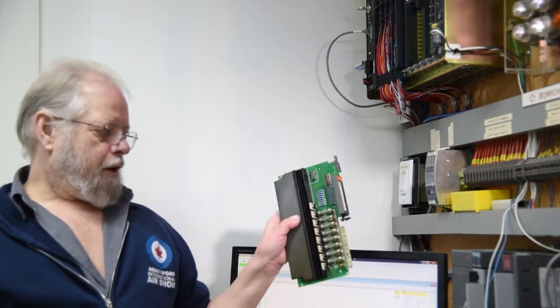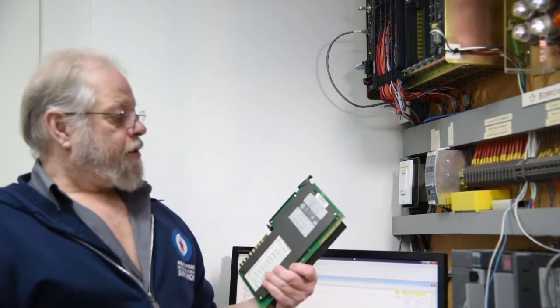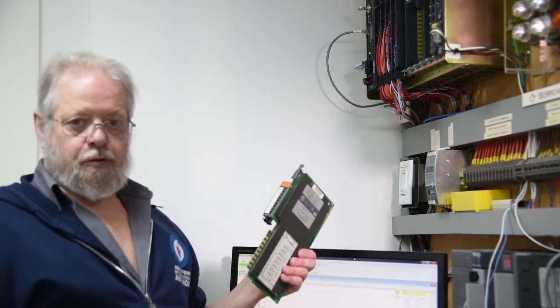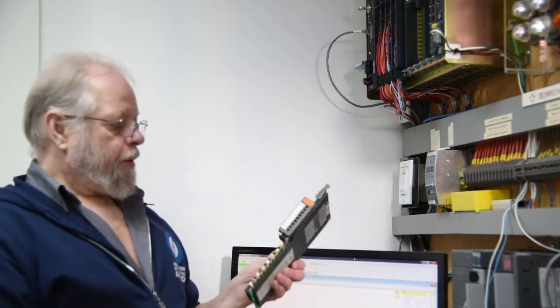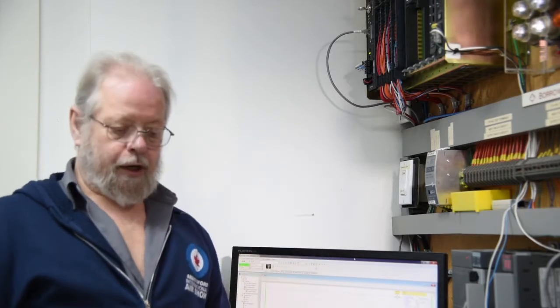Now, in the original 1771 OAD card, especially the Series A, and this is a Series B so they were a little bit better, the triacs had terrible leakage.